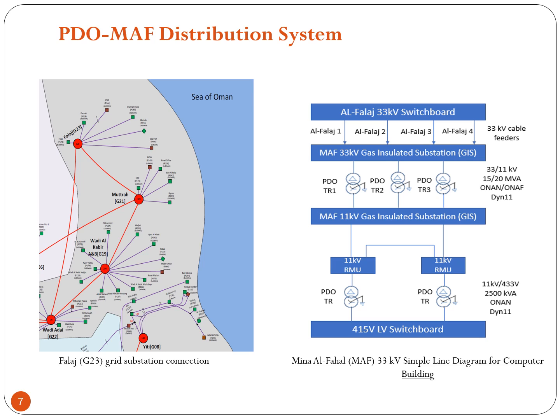PDO-MAF 33 kV consists of 3 transformers, 15/20 MVA 33/11 kV power transformers installed in the 33 kV bay, linked to the 11 kV Mina Al-Fahal GIS station. The 415 V LV substation and switchboard electricity supply is taken from 2500 kVA 11 kV over 433 V auxiliary transformers which are tapped from the 11 kV RMUs, as shown in the figures.